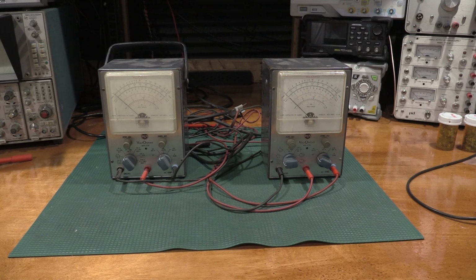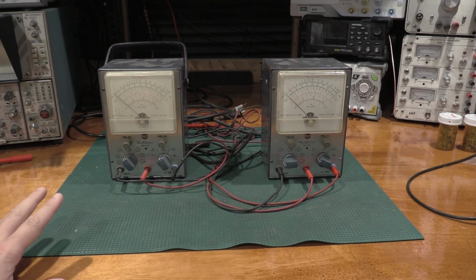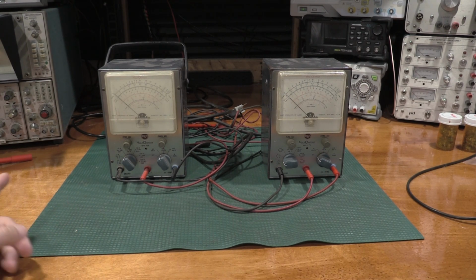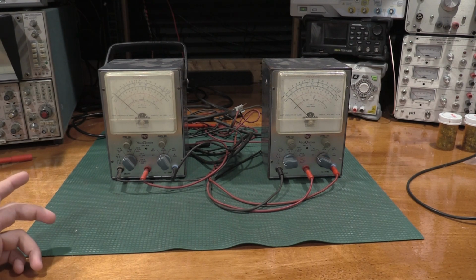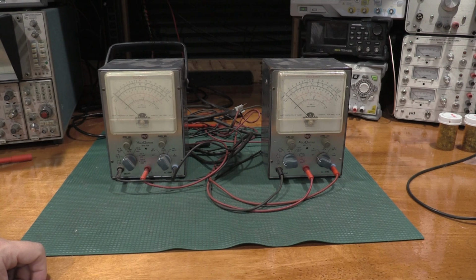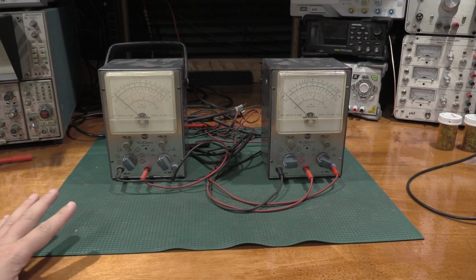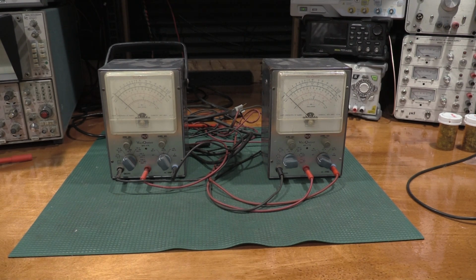Well, let's get this on, get it cracked. Let's check the meter movement. We can do that on the ohms range, and we'll crack it open. There is a battery in these meters, even though they have an electrical cord. Those batteries tend to off-gas and leak and do all kinds of damage to the inside of the meter, so hopefully we don't run into that. If you're going to decommission one of these meters and take it out of service, you definitely want to take that battery out. It does not do them any favors over time.